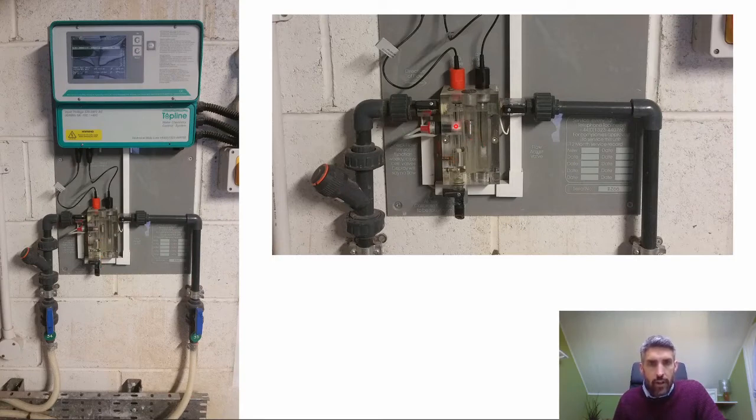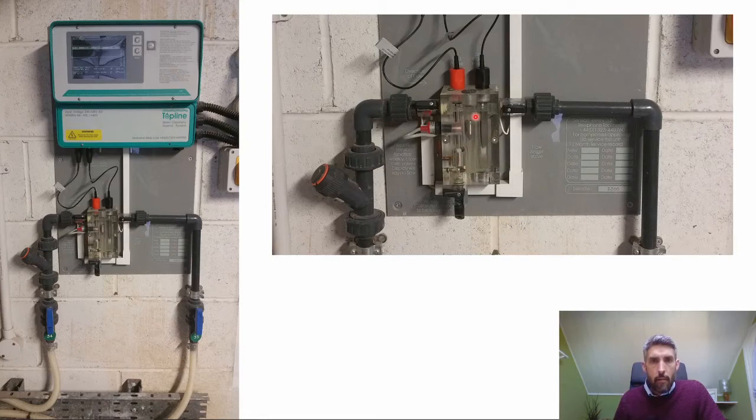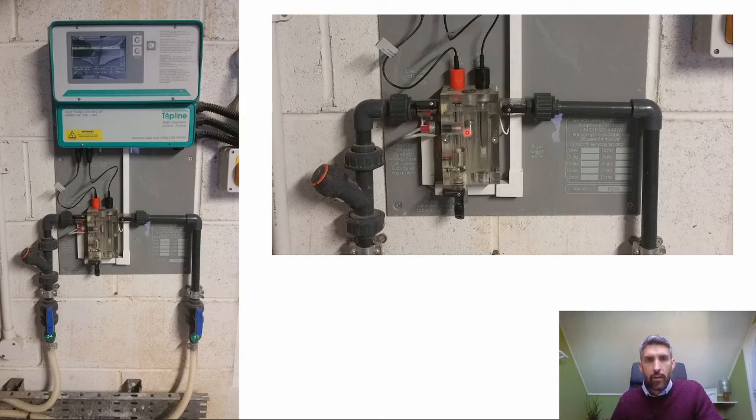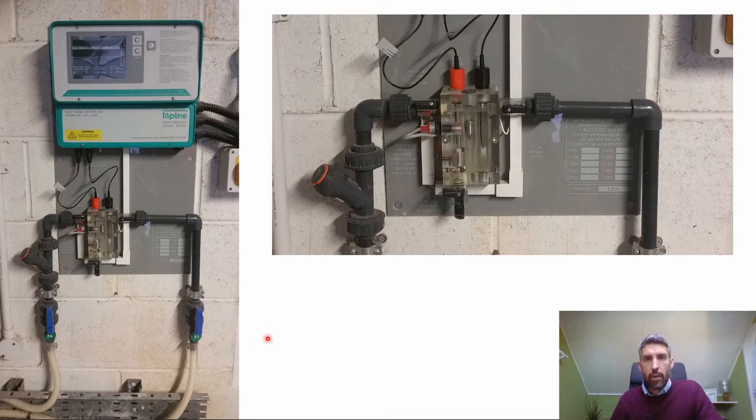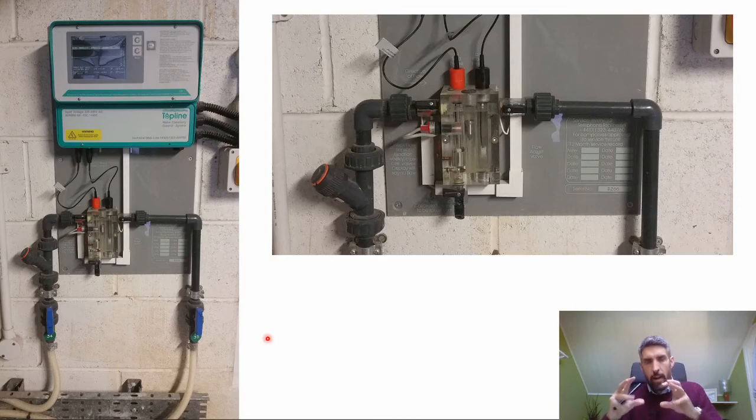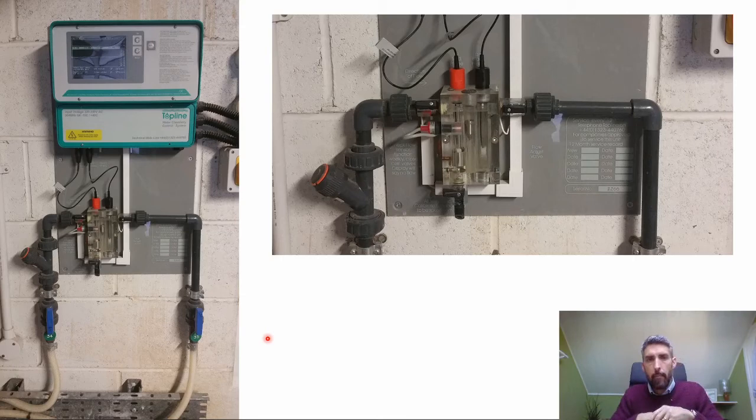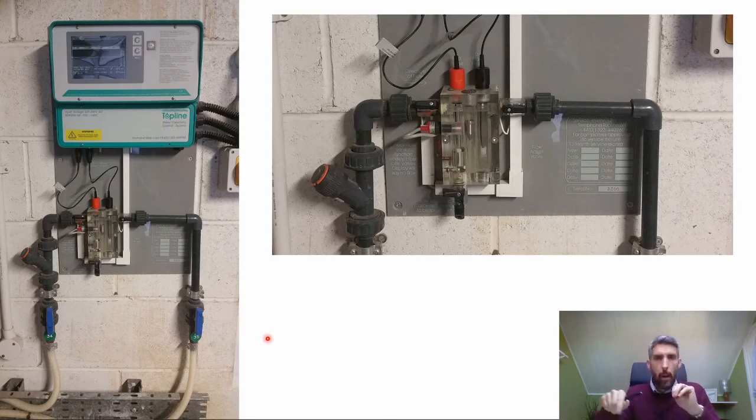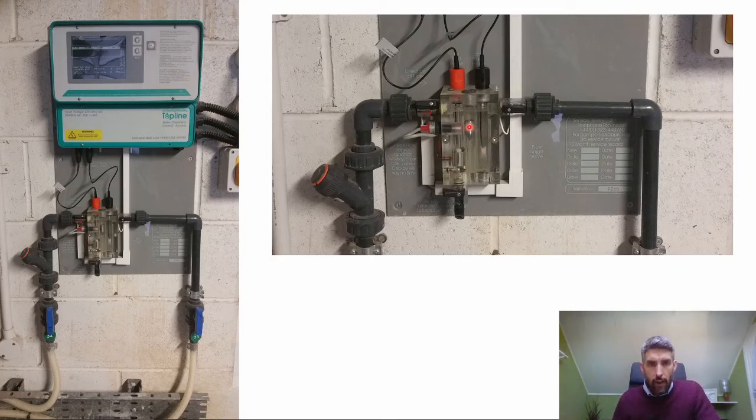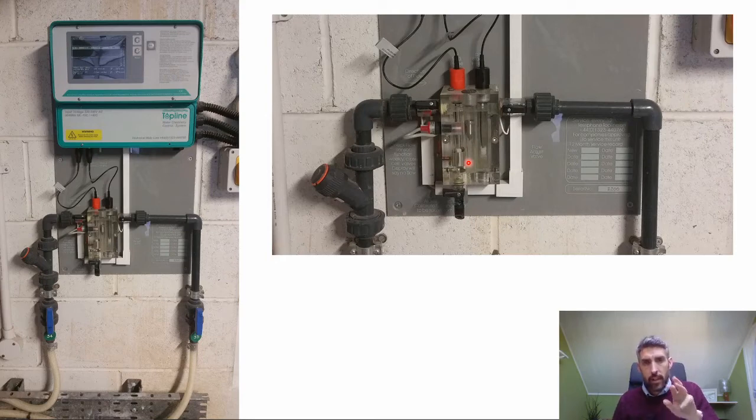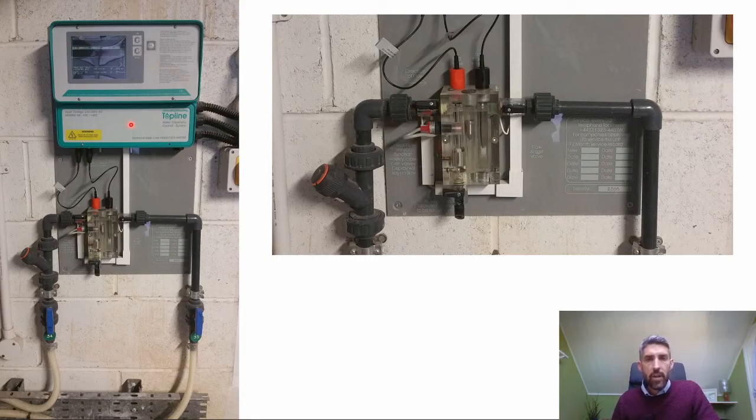For example, you've got the sample for testing being drawn through here off the pool through this sample cell, and then you've got the chlorine and pH probes here sending information to the control panel. Can you see that little metal bobbin? It's like a flow sensor—it's being suspended in that position because of the pressure on this sample loop. While the main circulation system has got water flowing through it, that little flow sensor will be suspended in that position. When the circulation pumps get switched off, there's no pressure going through this loop anymore, and that little float sits down.